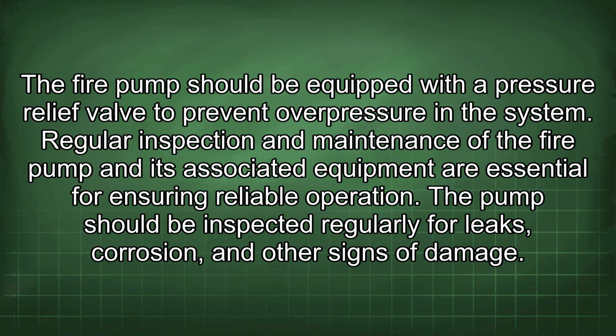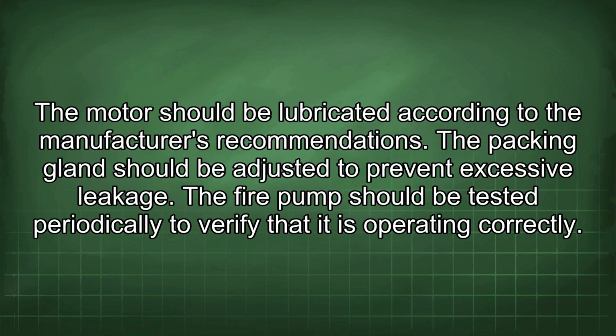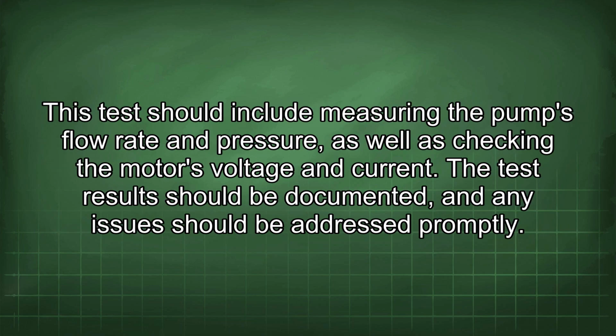Regular inspection and maintenance of the fire pump and its associated equipment are essential for ensuring reliable operation. The pump should be inspected regularly for leaks, corrosion, and other signs of damage. The motor should be lubricated according to the manufacturer's recommendations. The packing gland should be adjusted to prevent excessive leakage. The fire pump should be tested periodically to verify that it is operating correctly. This test should include measuring the pump's flow rate and pressure, as well as checking the motor's voltage and current. The test results should be documented, and any issues should be addressed promptly.